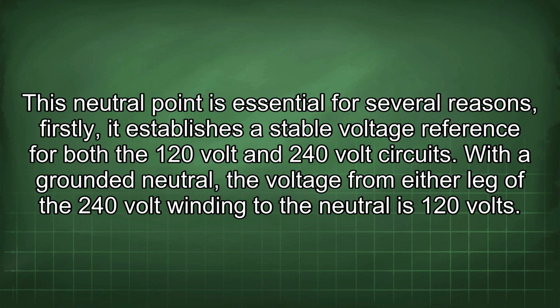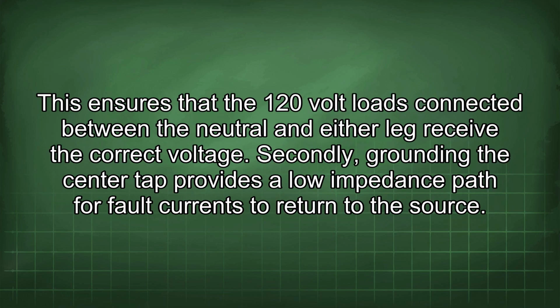Firstly, it establishes a stable voltage reference for both the 120 volt and 240 volt circuits. With a grounded neutral, the voltage from either leg of the 240 volt winding to the neutral is 120 volts. This ensures that the 120 volt loads connected between the neutral and either leg receive the correct voltage.